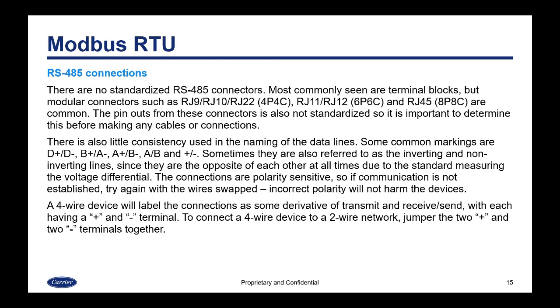With RS-485 there are no standardized connectors. Most commonly seen are terminal blocks, but modular connectors such as RJ-9, RJ-10, RJ-22 (a four-position modular connector similar to a handset jack on an old telephone), RJ-11, RJ-12 (a six-position connector similar to a telephone jack), and RJ-45 (similar to an ethernet connector) are common. The pin-outs from these connectors are also not standardized, so it is important to determine this before making any cables or connections. There is also little consistency in the naming of the data lines — common markings include D+ or D-, B+ with A-, A+ and B-, AB, or just + and -. Sometimes they are referred to as the inverting and non-inverting lines, since they are the opposite of each other at all times due to the standard measuring of the voltage differential.